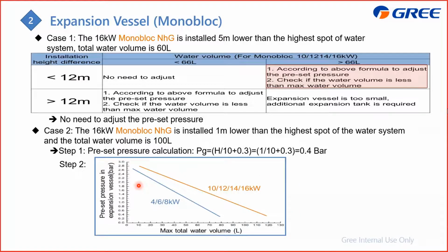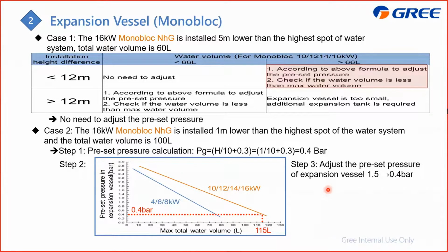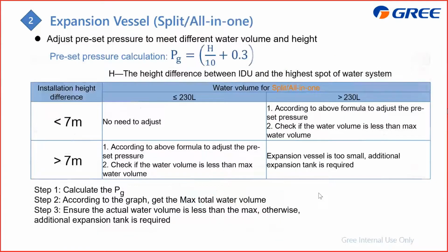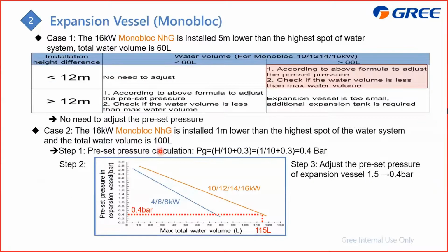And from this graph, you can also find the max total volume for the X, and the preset pressure of the expansion vessel is this one, Y. So this is the 0.4 bar, and you can get 115 liters, which is higher than 100, so it can cover this one.